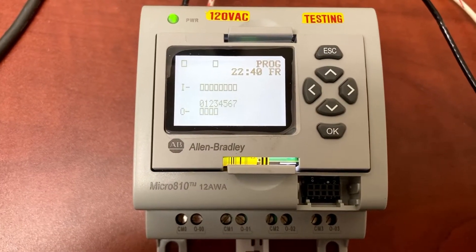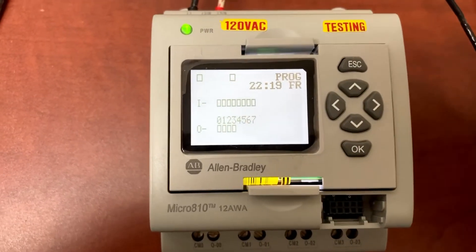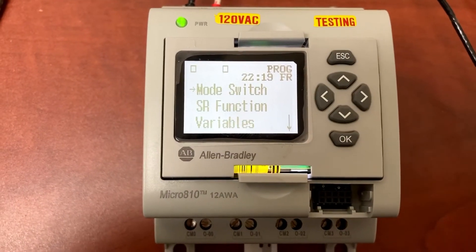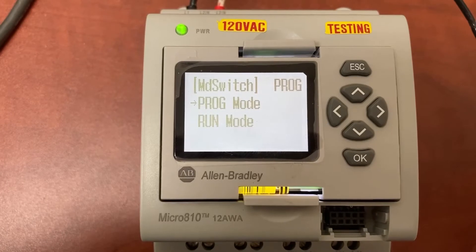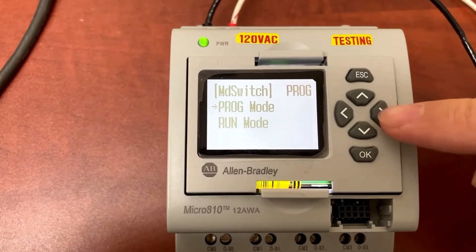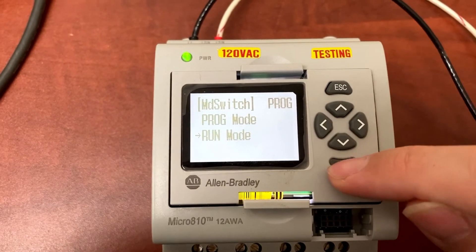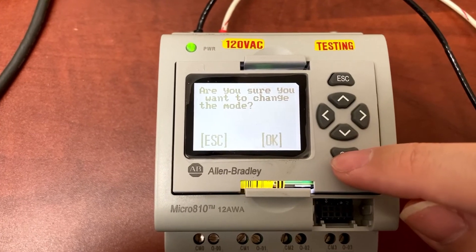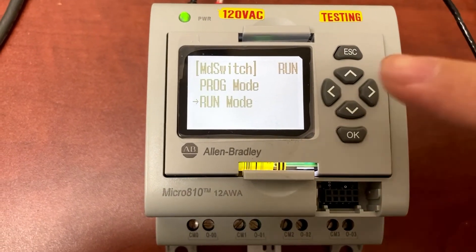To put it back to run mode, press Esc and OK together again. Press OK to go to mode switch. Select run mode, then press OK multiple times to confirm. You see, it's now back to run mode.